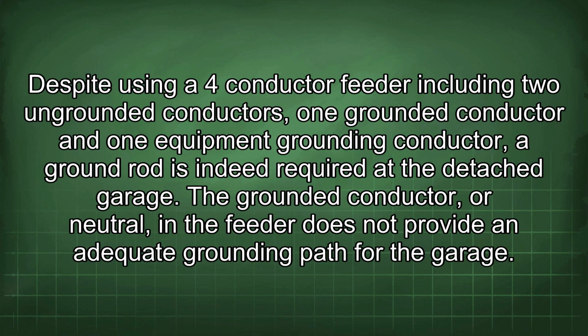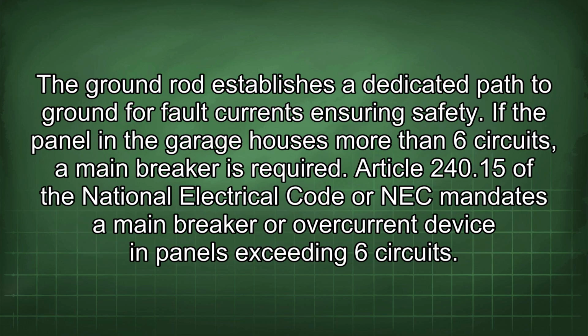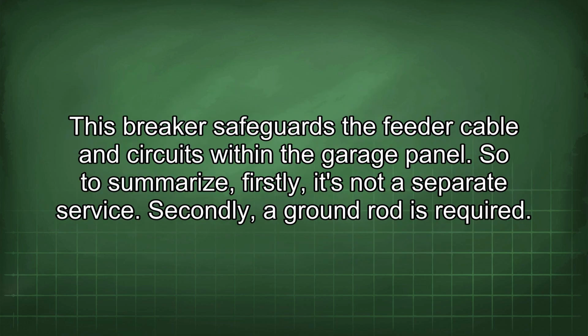The grounded conductor, or neutral, in the feeder does not provide an adequate grounding path for the garage. The ground rod establishes a dedicated path to ground for fault currents, ensuring safety. If the panel in the garage houses more than 6 circuits, a main breaker is required. Article 240.15 of the National Electrical Code, or NEC, mandates a main breaker or overcurrent device in panels exceeding 6 circuits. This breaker safeguards the feeder cable and circuits within the garage panel.